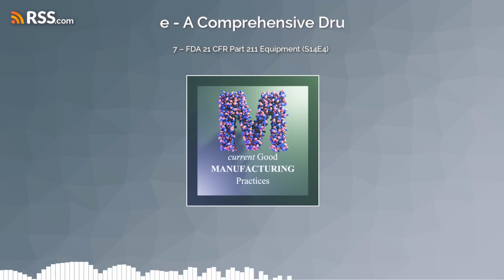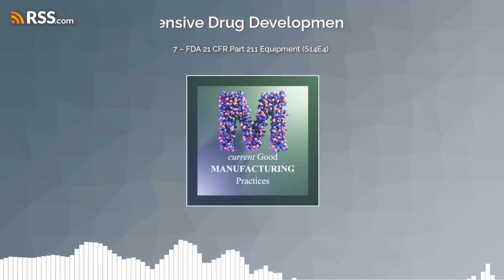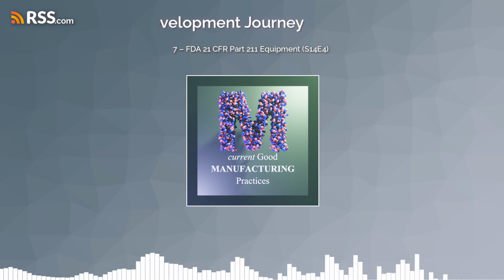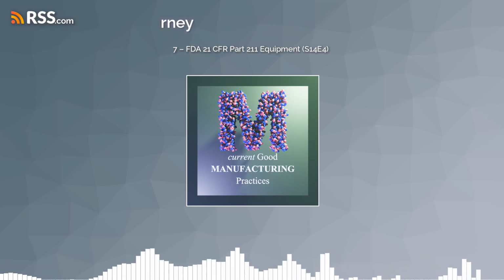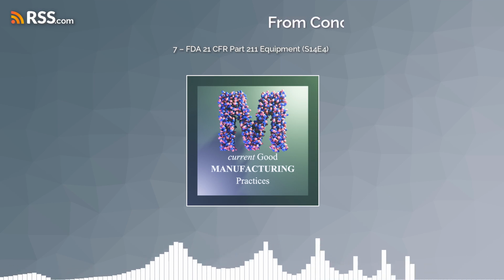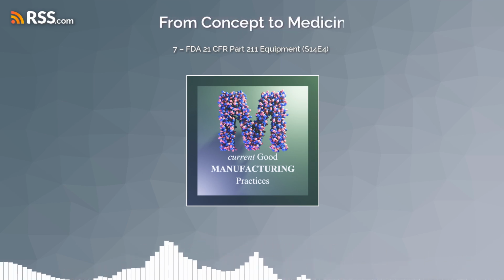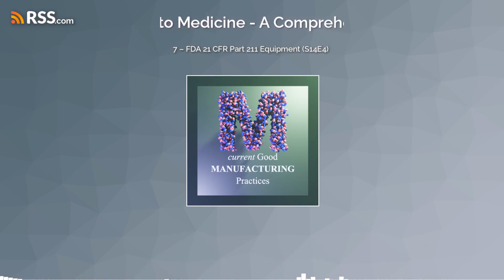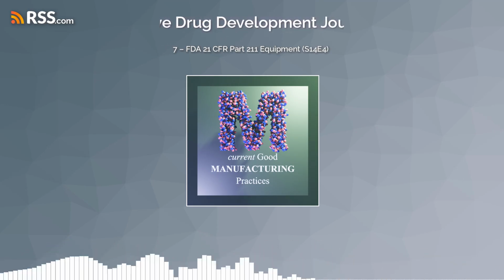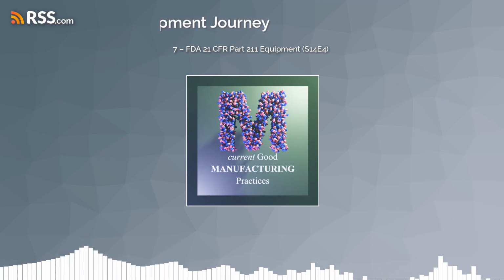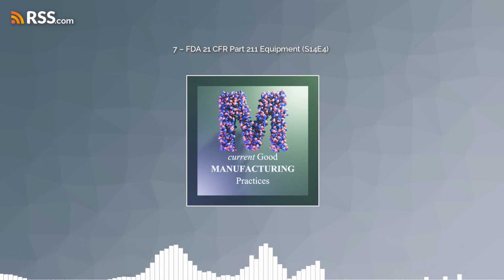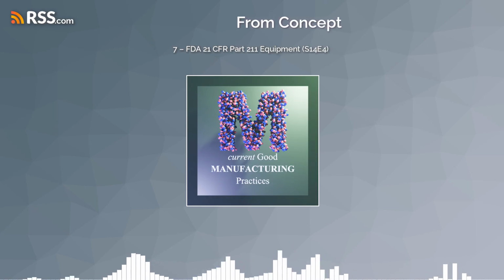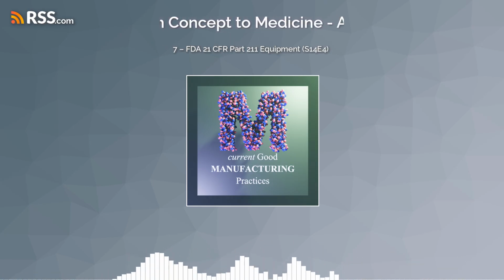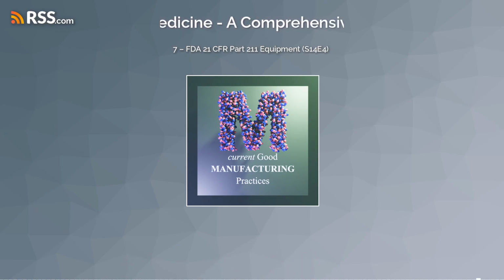Yeah. Now, what about performance qualification, or PQ? What happens there? PQ is the final stage. It's where you really put the equipment through its paces. You're simulating real-world production conditions to demonstrate that the equipment can consistently produce products that meet those required specifications, even under pressure. So it's not just testing in a controlled lab setting. You're trying to mimic what it'll be like out on the manufacturing floor. Exactly. You'd be running the equipment with the actual product, adjusting the operating parameters, and basically challenging it to see if it can handle the variability of real-world production. So it's like a final exam for the equipment. That's a great way to put it.